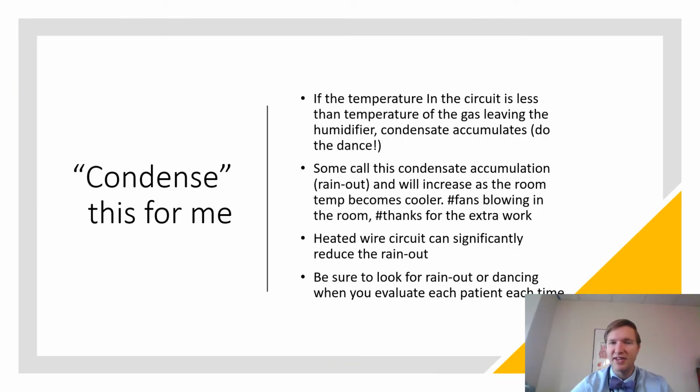All right, if the temperature in the circuit is less than the temperature of the gas leaving the humidifier, there's condensate that forms, right? That's water just jiggling around in that circuit. And that could cause a lot of issues with not only the gas flowing to the patient could be more turbulent, we could also have obstruction of gas flow, we could also see higher pressures, we could also see auto cycling where the ventilator decides to give more breaths than it should, right? And we can see that neonate through adults on the ventilator circuit. So that's something we got to be careful of, is that condensate that forms.